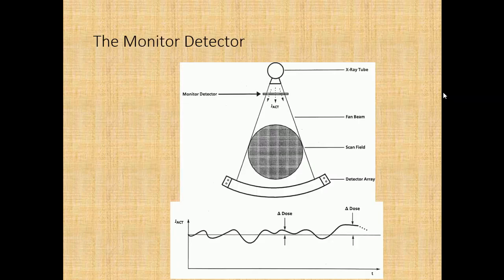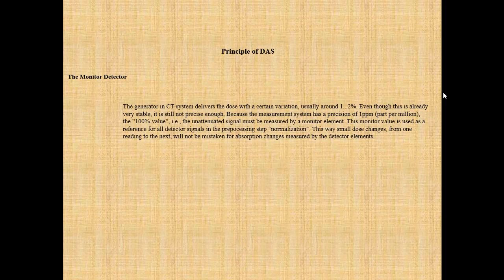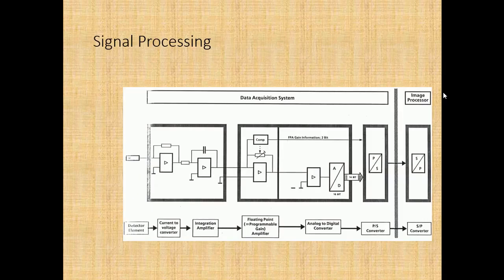The monitor detector: the generator in a CT system delivers dose with a variation of around 1-2%, which is not precise enough for the measurement system's required precision of 1 ppm (part per million). The 100% value, i.e., the unattenuated signal, must be measured by a monitor element. This monitor value is used as a reference for all detector signals in the pre-processing step of normalization, so that small dose changes are not mistaken for absorption changes measured by the detector elements.